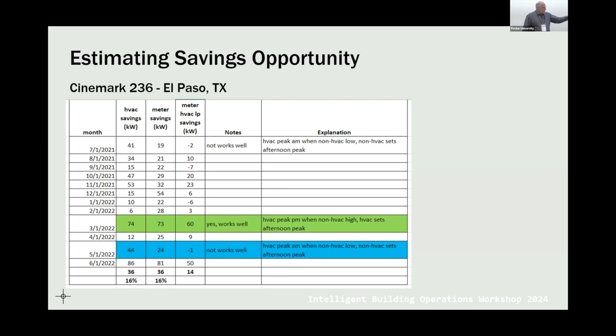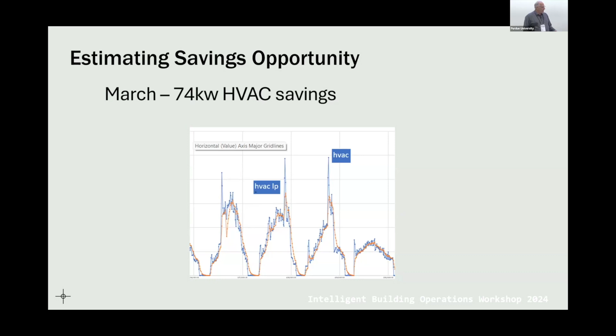This is March, where it worked. You can see when you look at the peak for the HVAC and then the low pass filter HVAC, it went down substantially. So it worked — 74 kilowatts of peak demand savings from just HVAC.